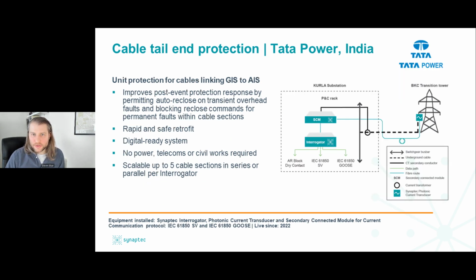So the final application I want to mention here is another example of where this technology is very well suited, and that's for protection of mixed or hybrid circuits, which have sections of both cable and overhead line conductors. So clearly it's beneficial to reclose for overhead line faults, for helping with overall security of supply, but it's also crucial to block auto reclose for cable faults. And conventionally, this is a difficult problem for utilities because installing remote measurements is expensive. So for this deployment, we installed a system in India, which had remote CTs at the transition point, and that essentially provides perfect discrimination of the faulted section.